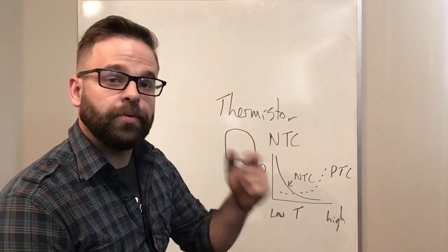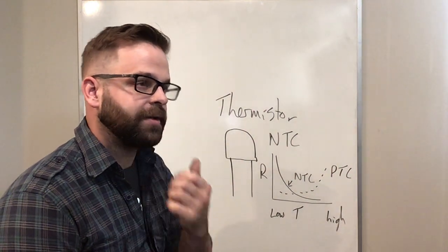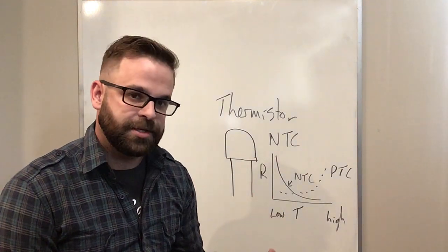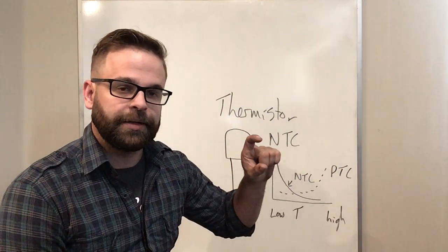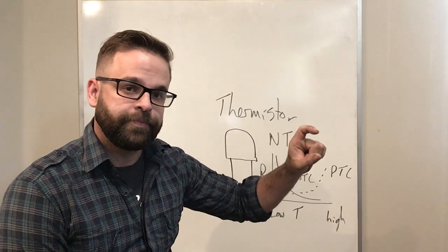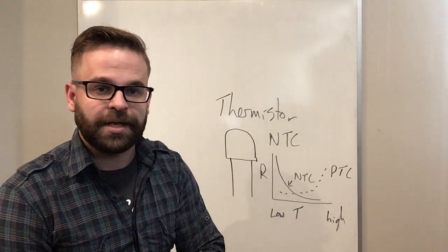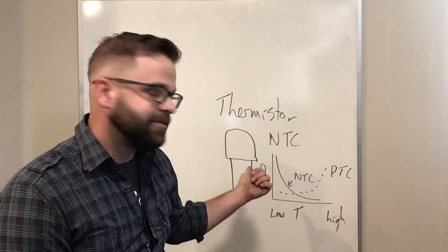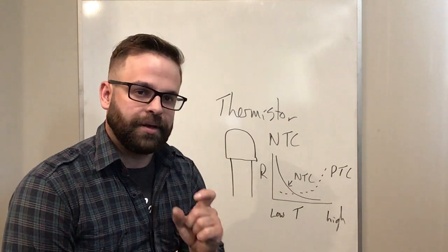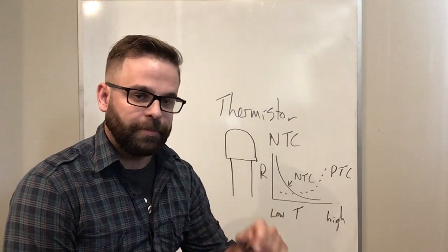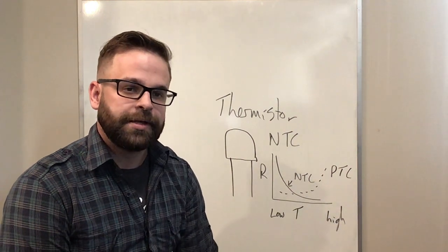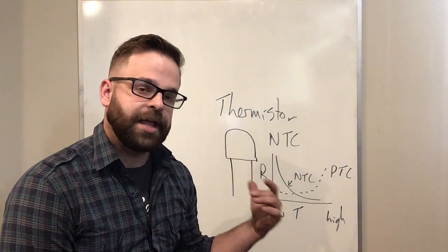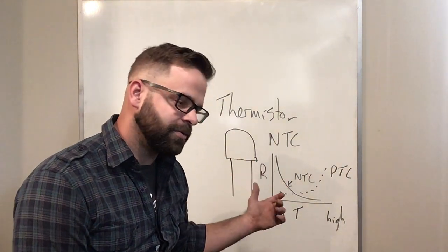Typically at restaurants or apartment buildings, if you don't want the customer to be able to change the temperature, you just put a little thermistor in the room, and it sends the signal back to the thermostat saying what the temperature is, so no one can screw with it. But the only thing, as I said, is it is very weak. They are in an enclosure, but if that ends up being ripped apart, obviously it won't work. So typically in a setting where there isn't a lot of chance for damage, I would put those in.